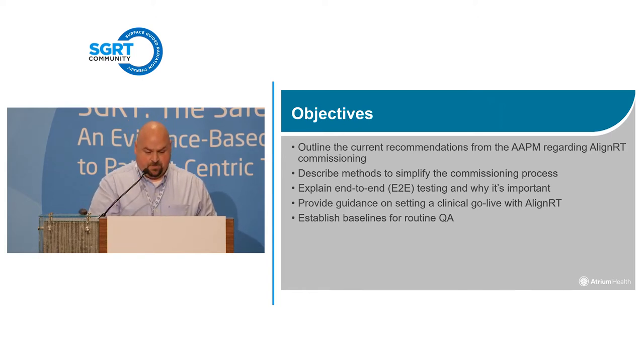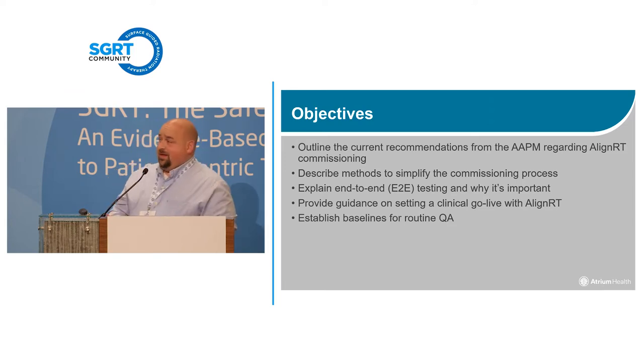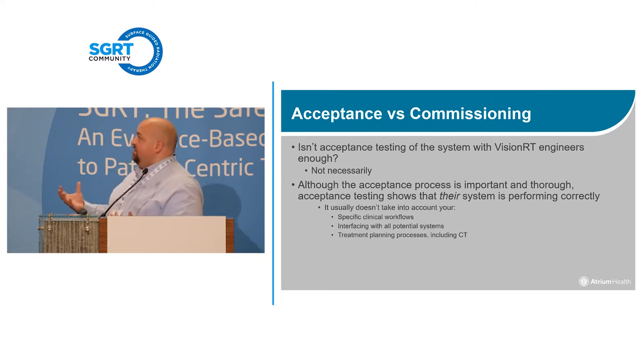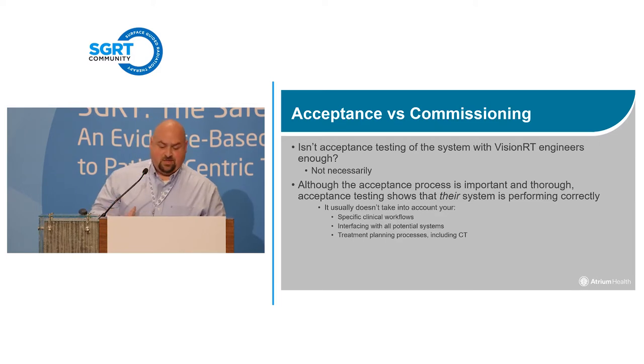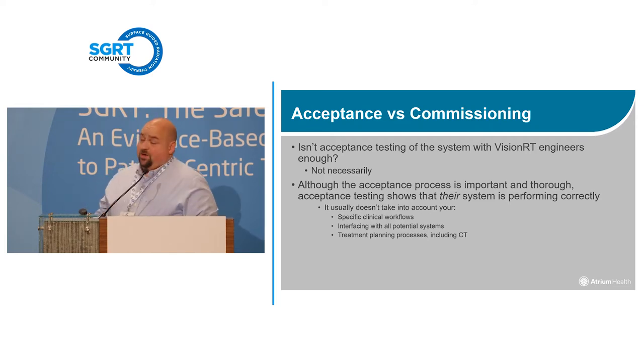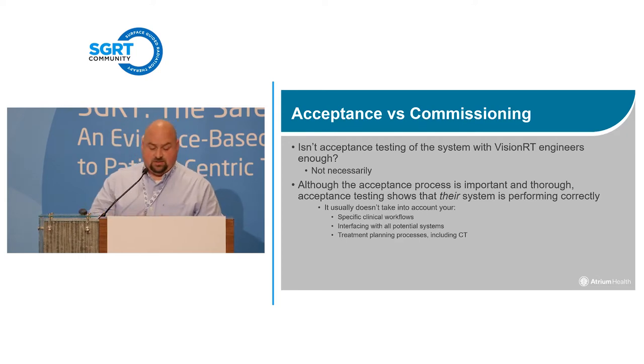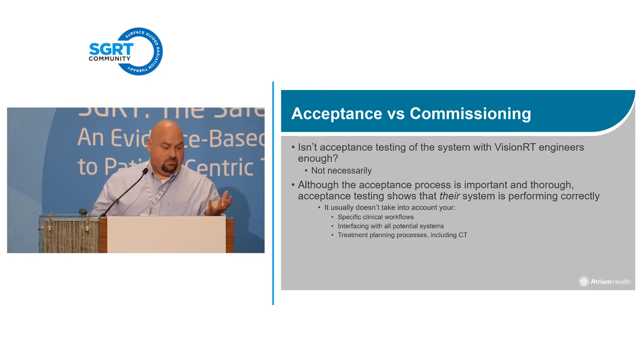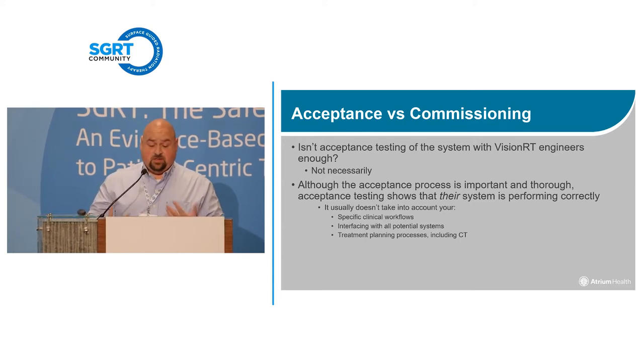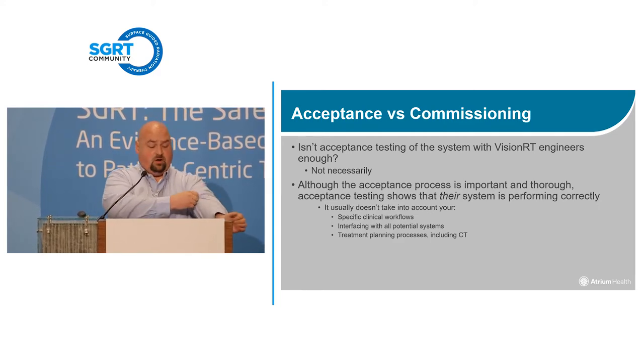It's easy to get swept up in everything, but back to basics: acceptance versus commissioning — what's the difference? A vendor comes out, does testing with a phantom, shows the system meets specs. Is that enough? Not really. It doesn't take into account specific clinical workflows. There have been many talks about extremities, SRS, treating a trigeminal — those all have their own clinical baggage. You need to test those things, including system interfacing, which is on the physicist to prove.